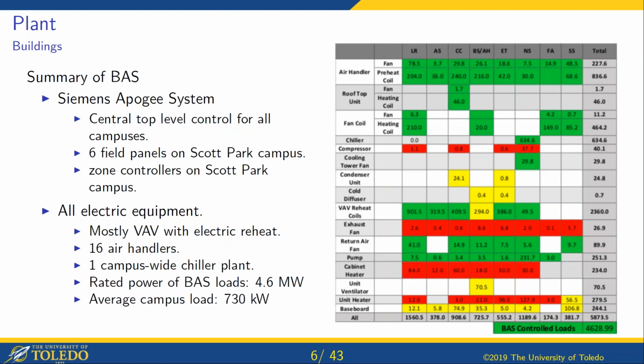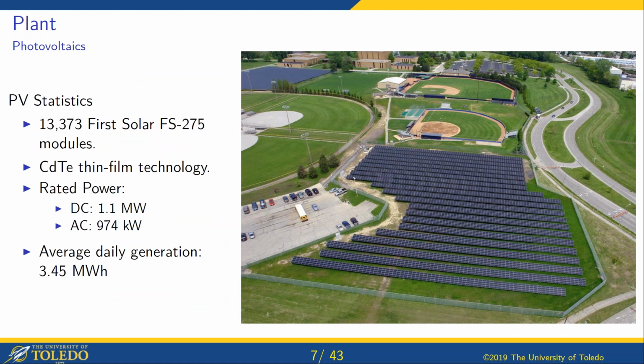It's all electric equipment - when this was installed, they didn't put in any gas. We mostly have VAVs with electric reheat. There are 16 air handlers on campus and a campus-wide chiller plant. The rated power on campus is around 4.6 megawatts, and the actual average load is about 730 kilowatts.